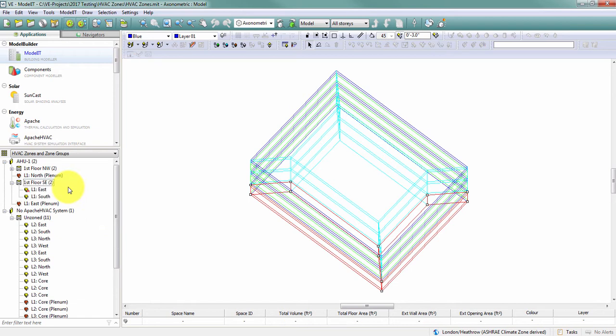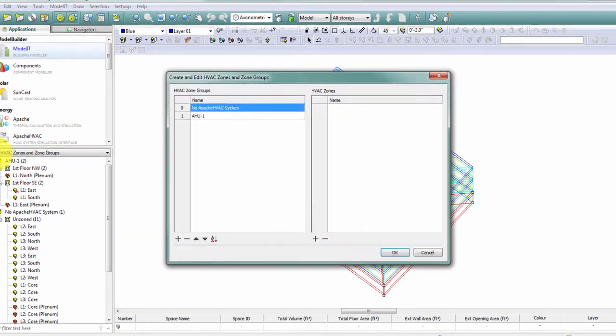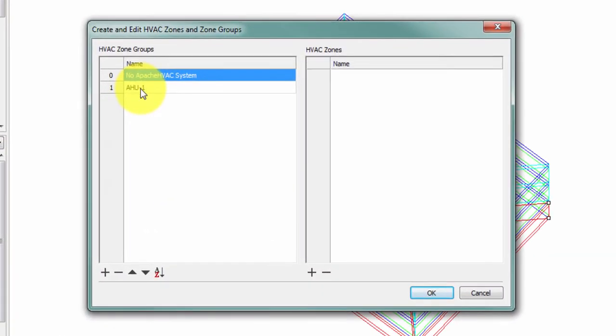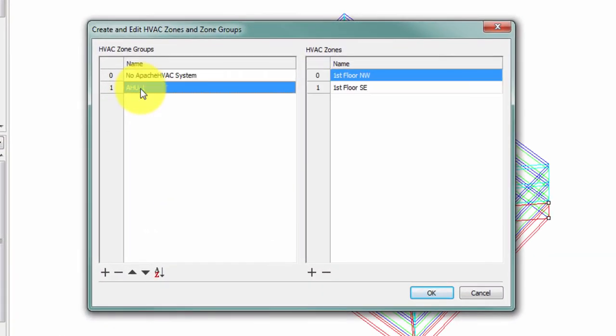Those are all of the zones that are going to go on my AHU1 zone group. So I need two more zone groups to represent the two other air handling units I intend to have on this project. There's two ways I can create more zone groups. In the create and edit dialog, I can edit my zone and zone groups the way that I've always edited room groups in previous versions of the software.